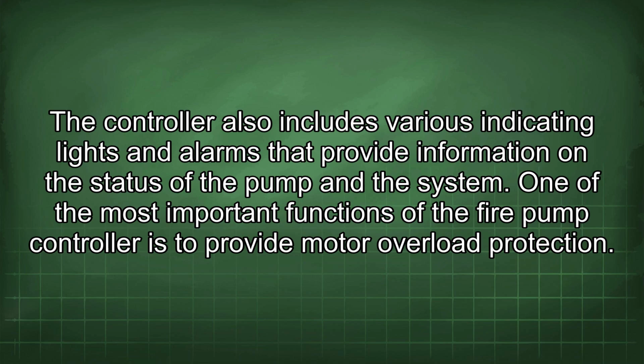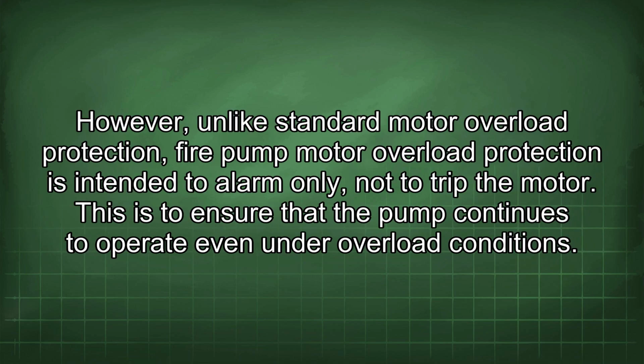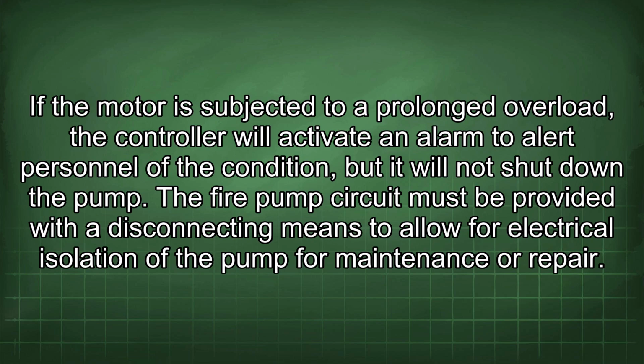One of the most important functions of the fire pump controller is to provide motor overload protection. However, unlike standard motor overload protection, fire pump motor overload protection is intended to alarm only, not to trip the motor. This is to ensure that the pump continues to operate even under overload conditions. If the motor is subjected to a prolonged overload, the controller will activate an alarm to alert personnel of the condition, but it will not shut down the pump.